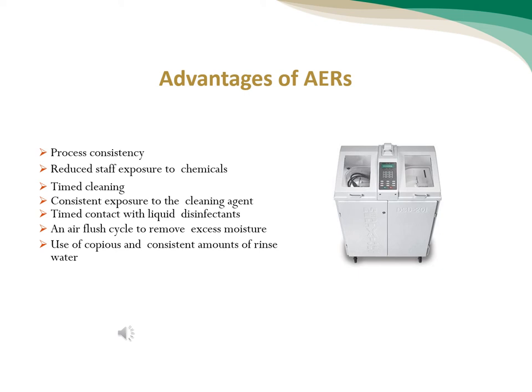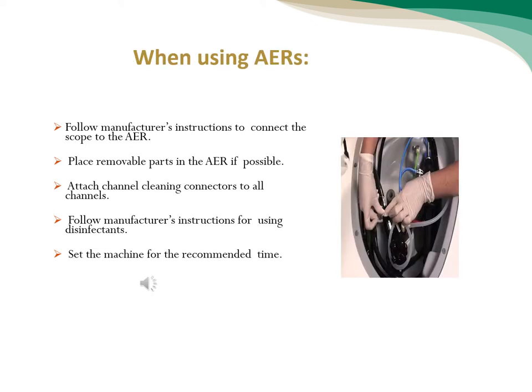When using an automated endoscope reprocessor: follow manufacturer instructions to connect the scope to the AER, place removable parts in the AER if possible, and attach channel cleaning connectors to all channels.